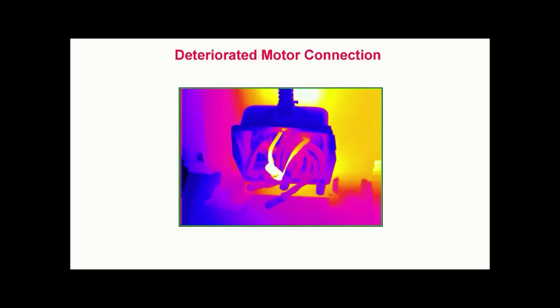Deteriorated motor connection. Here we see a thermal pattern caused by a loose or deteriorated electrical connection within the junction box of a motor. Since thermal imagers cannot see through solid materials, the junction box cover has been removed to provide a clear line of sight to the connections.